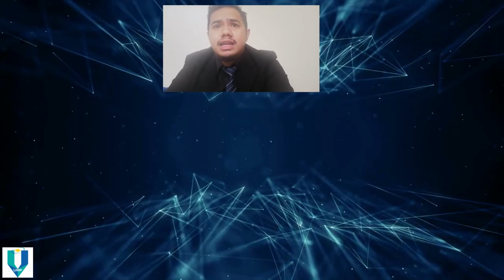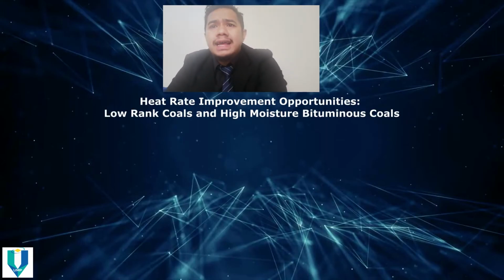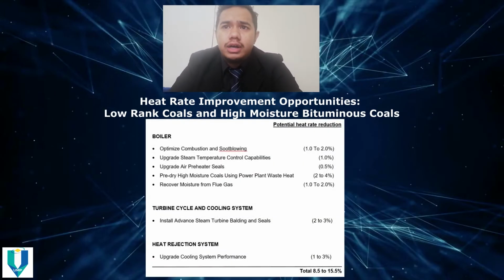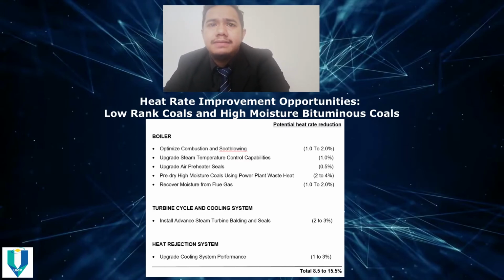Second, the heat rate improvement opportunities for low rank coals and high moisture bituminous coals. First, for the boiler, the optimized combustion and soot blowing is from 1 to 2%. For upgrading steam temperature control capabilities, it is 1%. Upgrading air preheater seals is 0.5%. Pre-drying high moisture coals using power plant waste heat gives 2 to 4%. And recovering moisture from flue gas is from 1 to 2%.